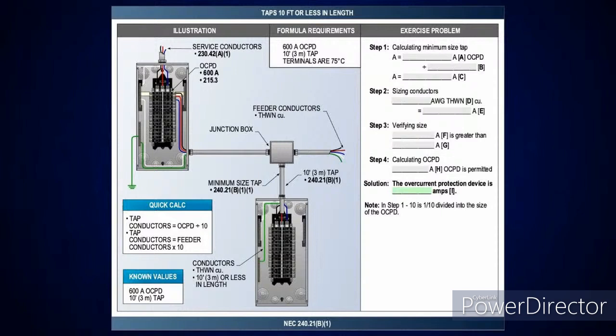Okay. But what I like to point out, we did this on conductors a couple of weeks ago. And if you notice, I'm still doing the exact same thing. I'm not changing anything in the way that I do it. All I did earlier, we sized the conductors. Now we're doing the overcurrent device and telling you what the minimum size conductors and overcurrent protection device would be. But you're still performing the exact same type of calculation.